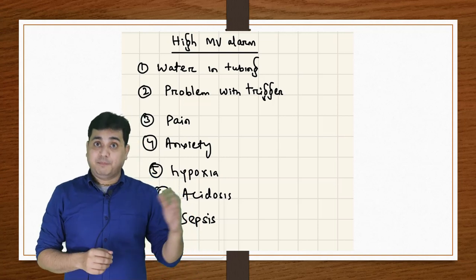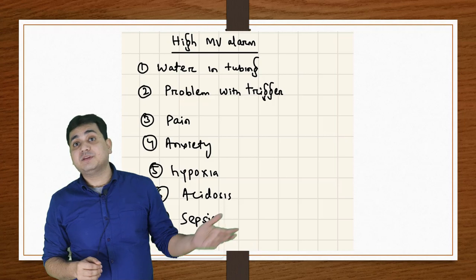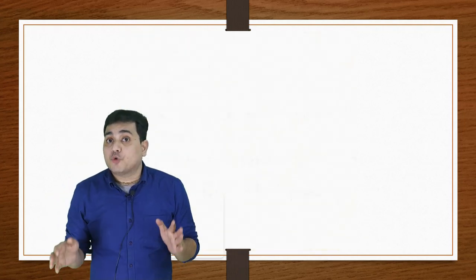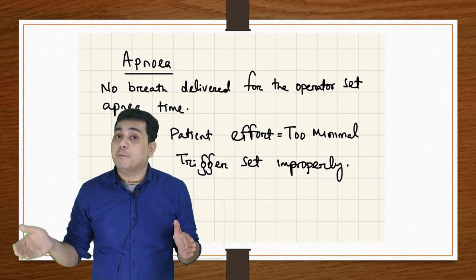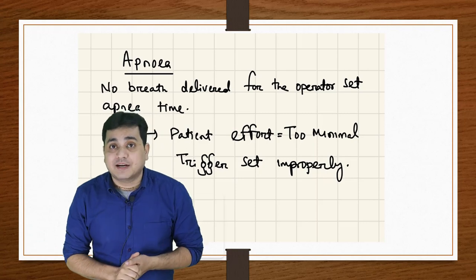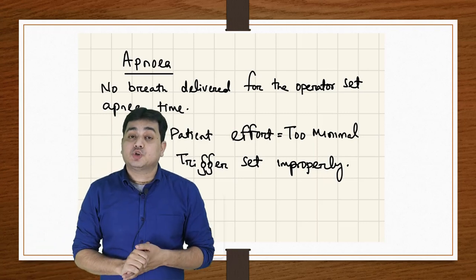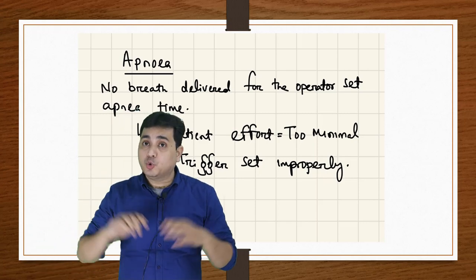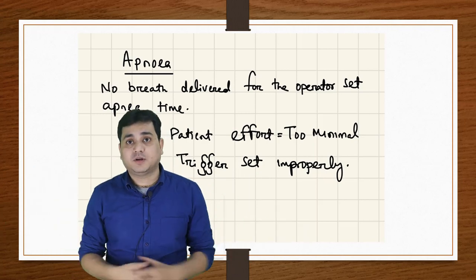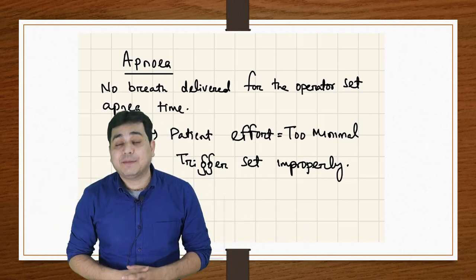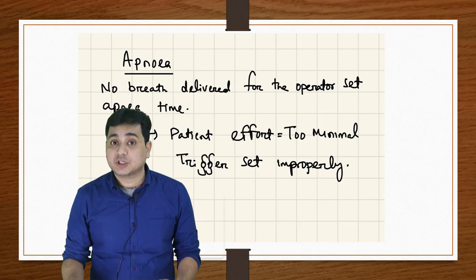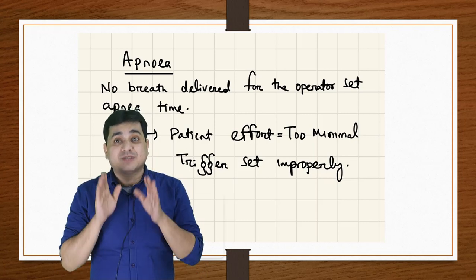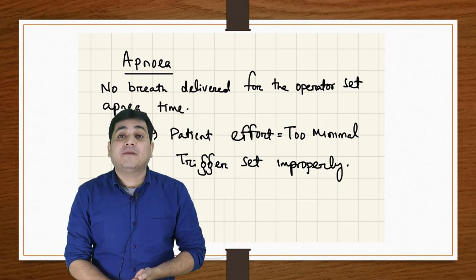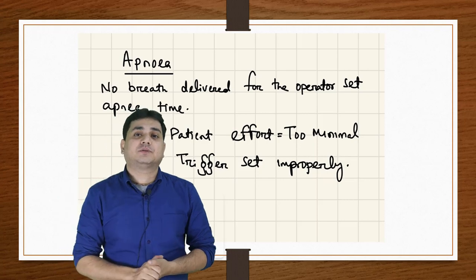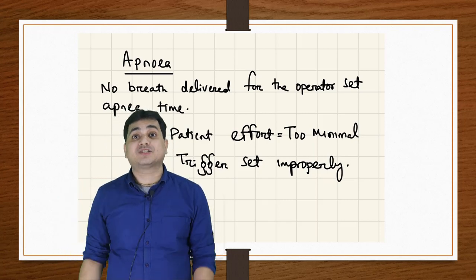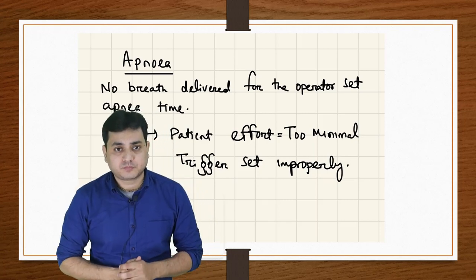Correct? Then you have the apnea alarm. Of course, apnea alarm means if the patient is not breathing, then the ventilator will back up with a time ventilation or control ventilation. So it has to be set appropriately, not too high, not too long. Otherwise, the patient will have apneic episodes and can have cardiac arrest. So the apnea alarm has to be set appropriately, at least in pressure support ventilation, where we want the patient to be conscious and breathing on their own.